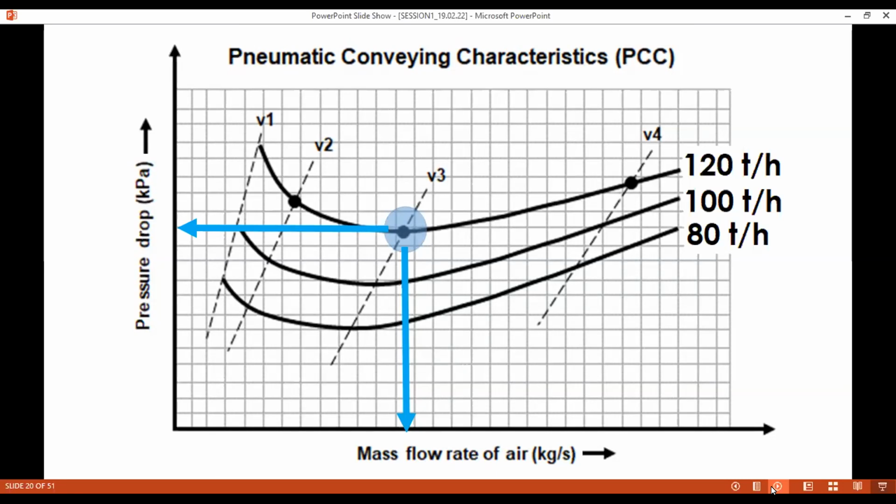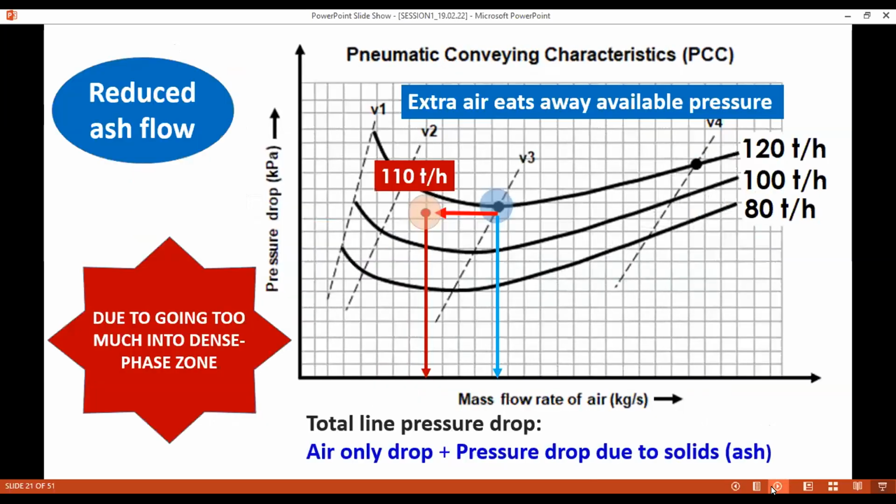Now, if you have got an under capacity system in your plant, so what your supplier has given you, instead of that ideal pressure minima point, he wanted to reduce the compressor capacity, and instead of giving you that blue shaded line point, he has given you a less mass flow rate of air, because you wanted to reduce that compressor capacity, obviously, for certain reasons.